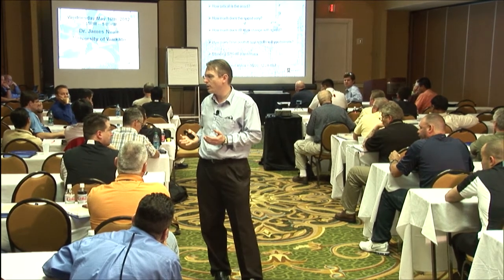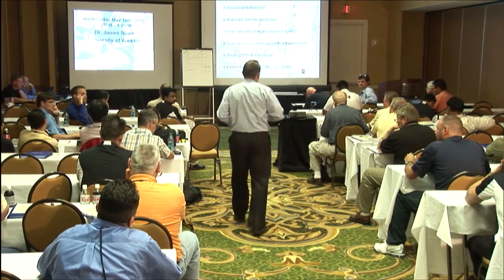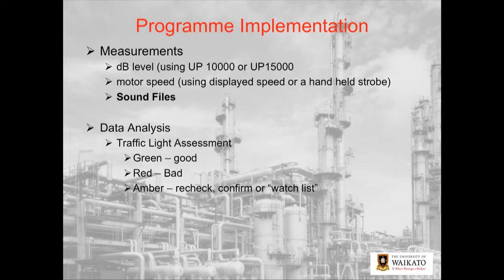So you're thinking, well, the bearing seems okay. So you're going to think, well, hey, it's a little bit high. We may need to add it to our lubrication list, but we're not going to get too alarmed, right? But to be on the safe side, if we've managed to convince our boss to spring for a 10 or a 15, what else can we do? Record the sound, okay? And if you're fortunate enough to have the 15, you could bring up the spectralizer there and then on the spot, okay? Otherwise, you've got to go back to the office. But the point is, we can then use spectralizer to confirm what's going on, okay?